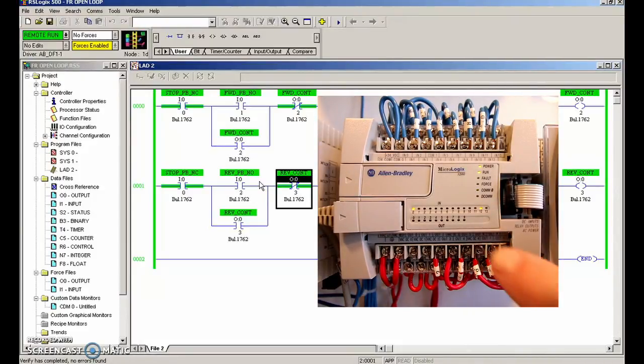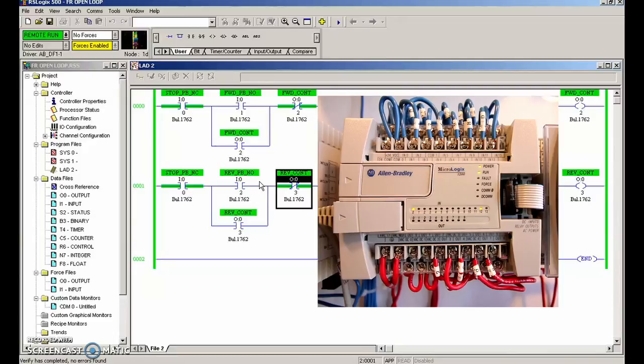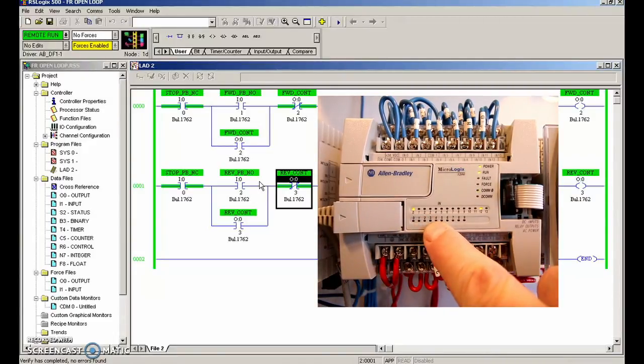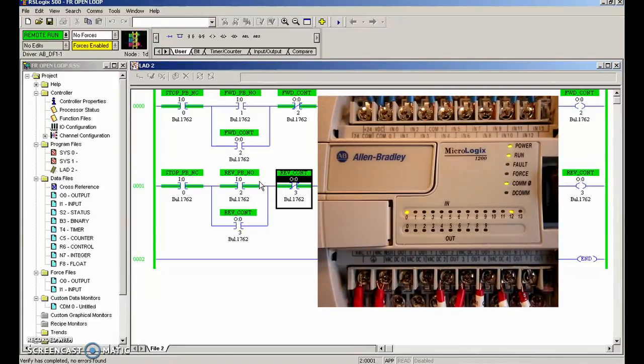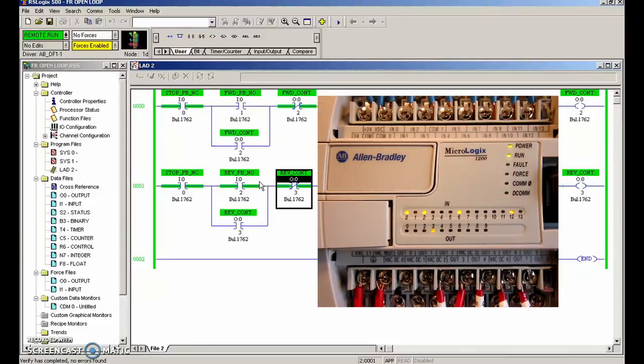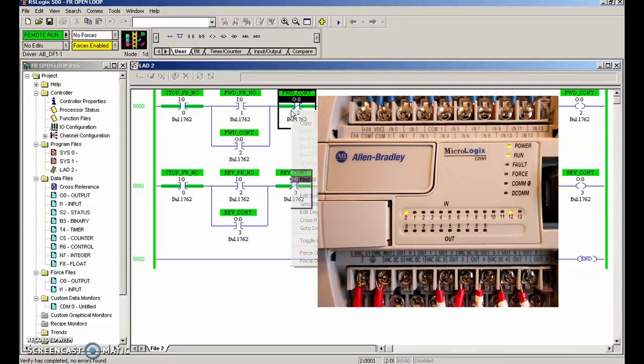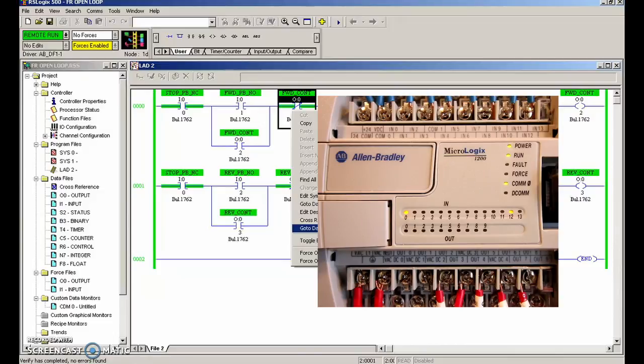Let's do it one more time in reverse to see if I've done the same thing there. My reverse contactor is output number three — let's zoom in on that LED. You can see the output is turning on and off so fast that the LED stays lit, and the contactor below is pulled in. When I let go, it should hold but it just kicks out. To fix this on the fly I haven't been able to figure that out — I can edit the symbol, go to the database, cross-reference, data table, but I can't change the output or input address there.